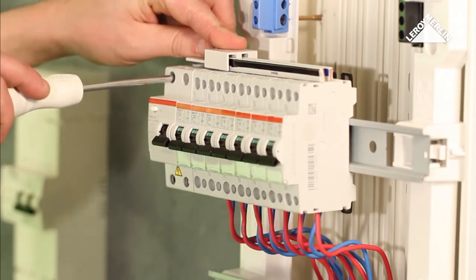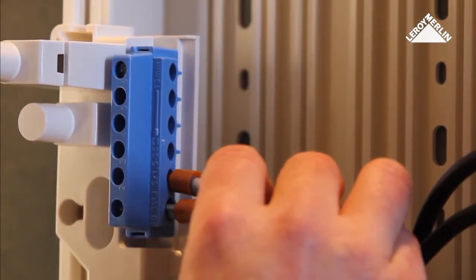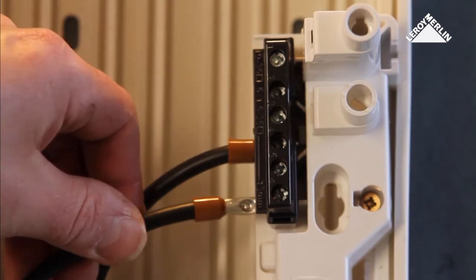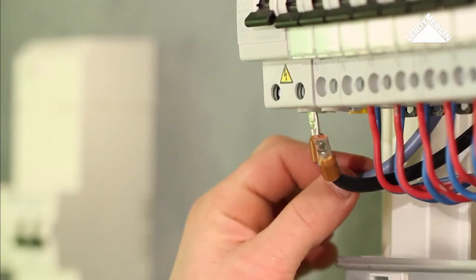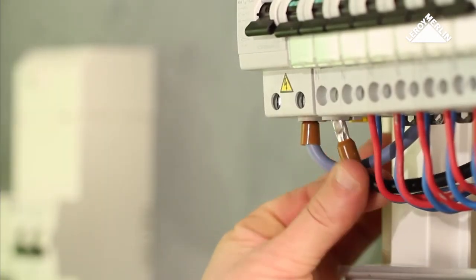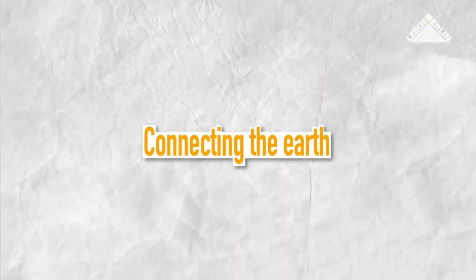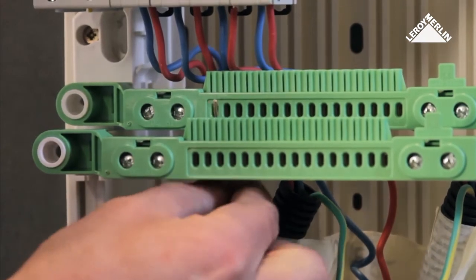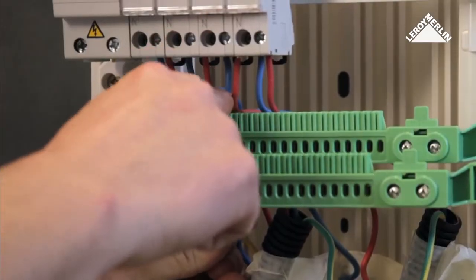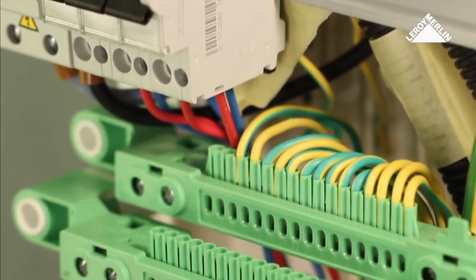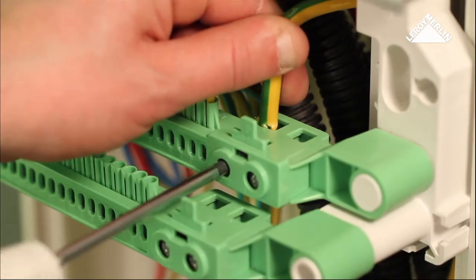There are 2 terminal blocks inside the distribution board, one for neutral and one for phase. Connect the phase and neutral cables coming from the circuit breaker. Then connect all the green and yellow cables at the bottom of the unit. These are the earth cables. Then, connect the earth circuit to the green terminal block.